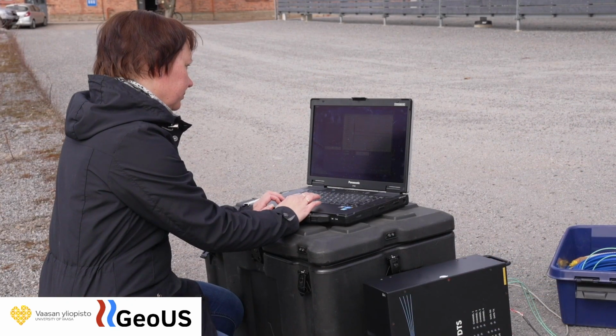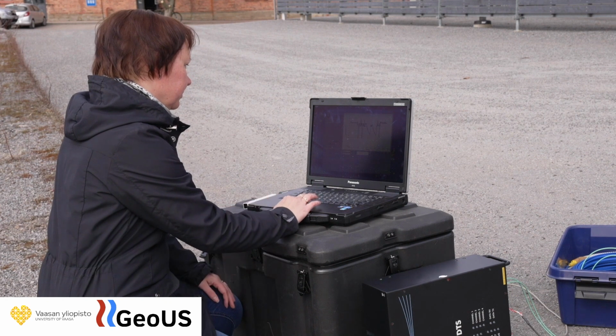Distributed temperature sensing (DTS) is based on the scattering of light in a glass fiber cable. It is a temperature measurement method where the optical fiber acts as a linear sensor. A measuring device sends short optical pulses of laser light, which encounter different types of scattering during their progression. A certain type, Raman scattering, is temperature sensitive. The measuring device determines the temperature at a certain point in the optical fiber with respect to anti-Stokes and Stokes photons and the optical pulse running time.